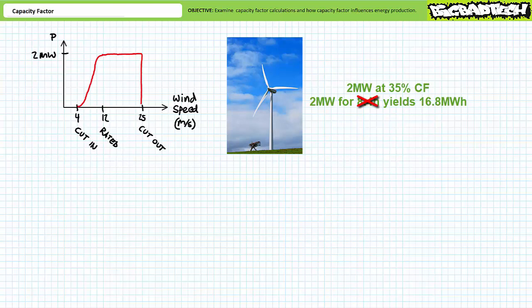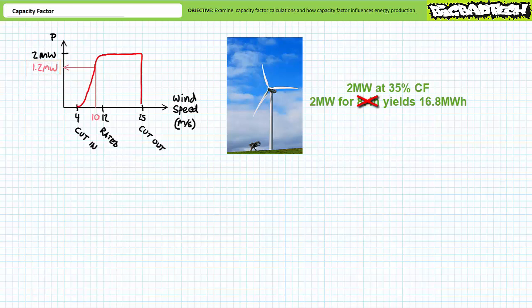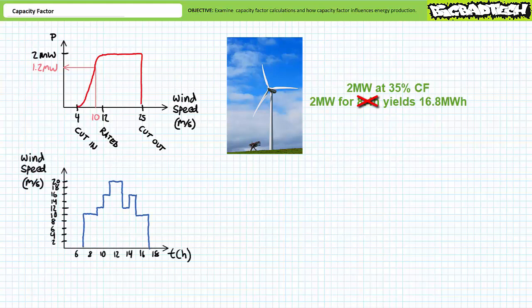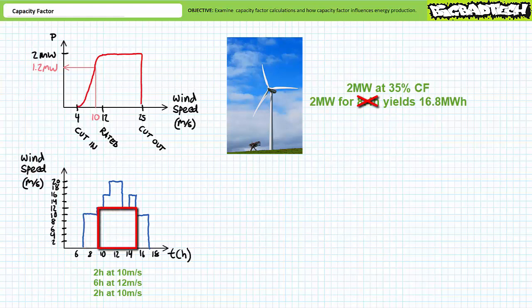At the rated speed, typically around 12 meters per second, the turbine generates its nominal or nameplate value. In this example, 2 megawatts. Between the rated speed and the cut-out speed, power flat lines at the nominal value. And finally, at the cut-out speed, typically around 25 meters per second, the turbine shuts down to prevent damage. Let's say at 10 meters per second, this turbine's output is only 1.2 megawatts. Let's now take a look at wind speed as a function of time for a particular day. To keep this problem manageable, let's say this turbine typically experiences wind speeds of 10 meters per second for two hours, then six hours of 12 meters per second or greater wind, and then the wind throttles back to 10 meters per second for another two hours.